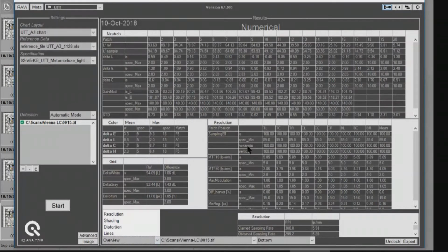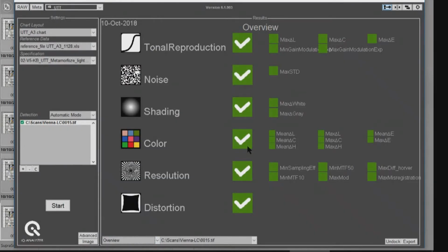That's the main thing. It's not a big problem if you spend a lot of time adjusting, as long as the results stay stable. You can spend time, I mean, that's what we did. You don't have to do it with this one because we provide the ICC profile, and the ICC profile has been adjusted to give the best result. And something you have to do anyway is, it's not enough, I would say, especially at the beginning, to say it's green, it's okay, because maybe you are very close to the limit somewhere.